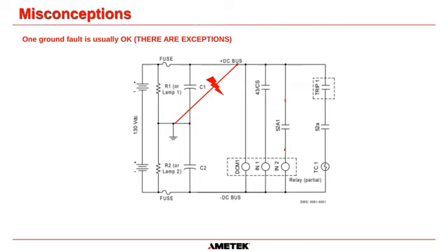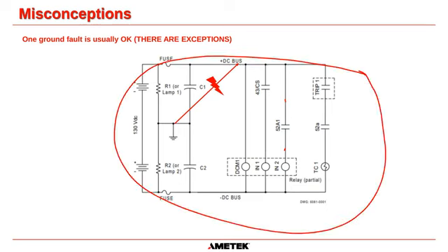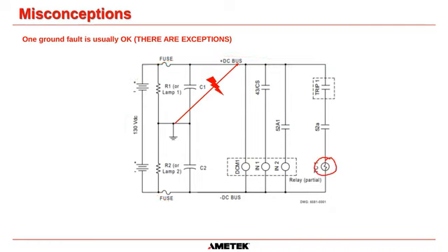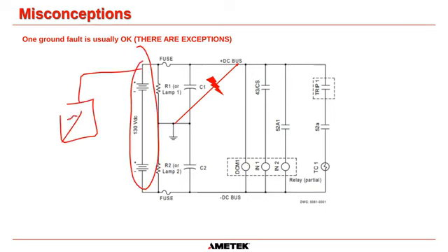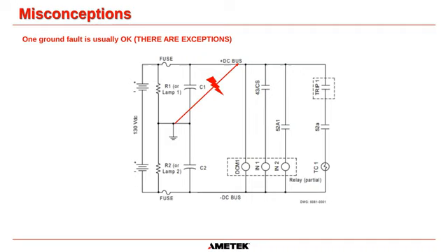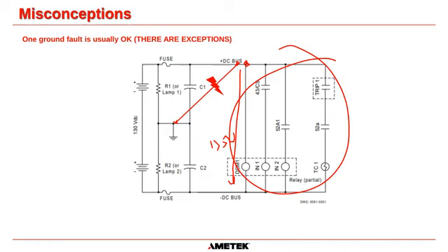So this circuit diagram here is a trip and close circuit on an MCC. Here's our trip coil, and there's trip signal, and there's other auxiliary contacts doing other stuff. And here's our battery on the left-hand side, which is actually going to be connected to a charger as well. So if we have a fault between the DC bus and ground, we're still going to have our 130 volts available for all of this circuitry here to work. That's not going to be affected. Everything is still going to work fine.